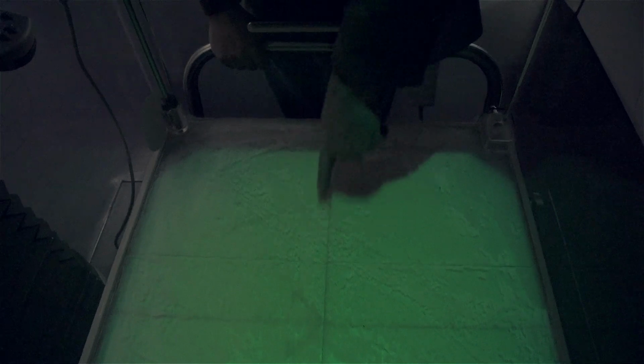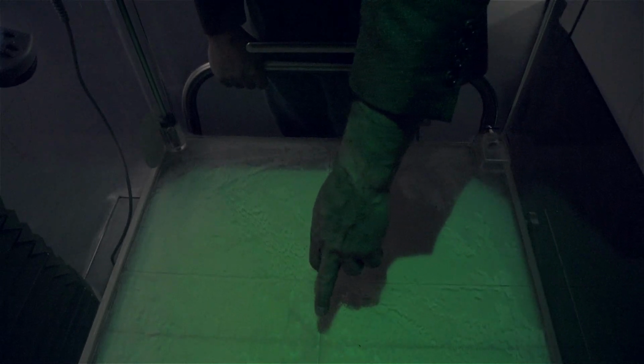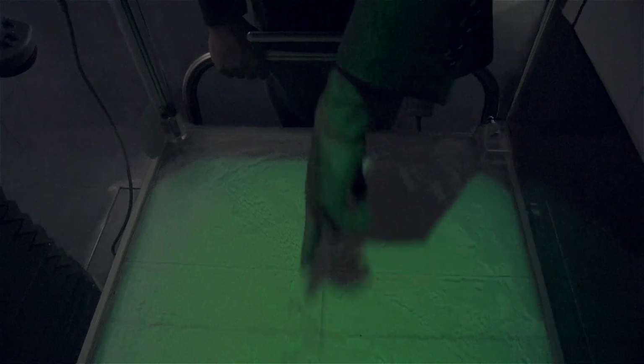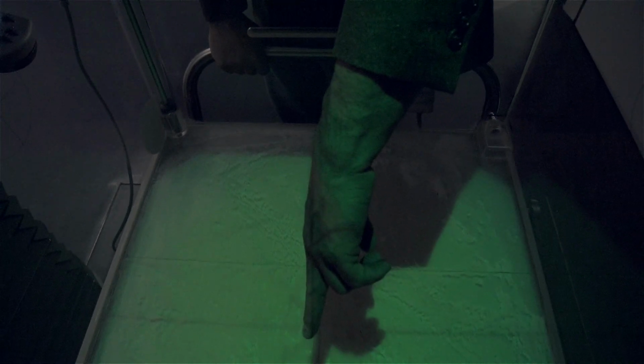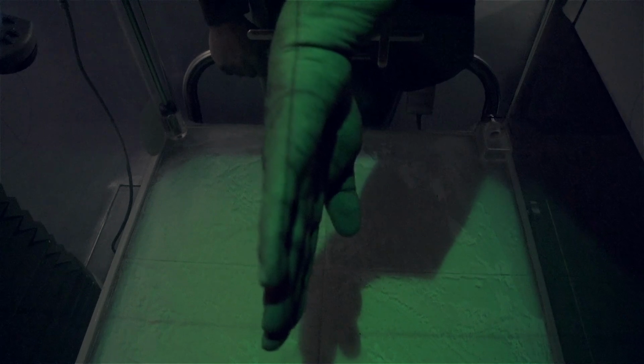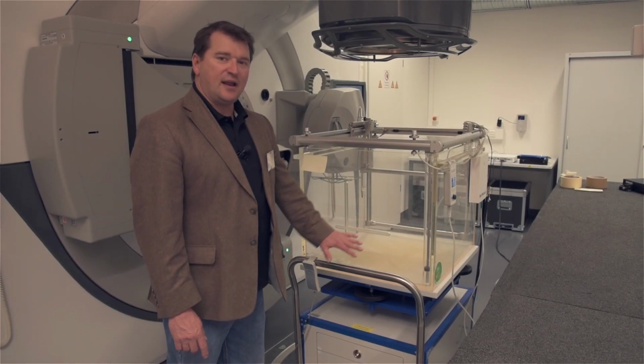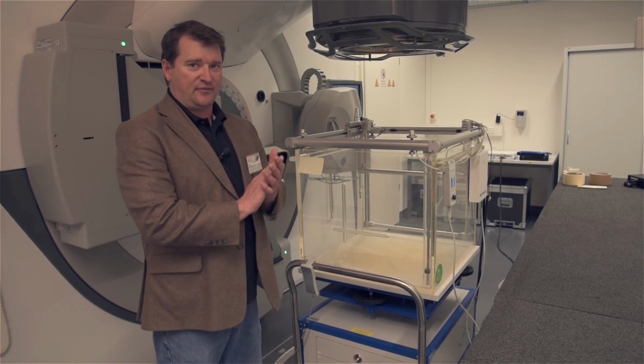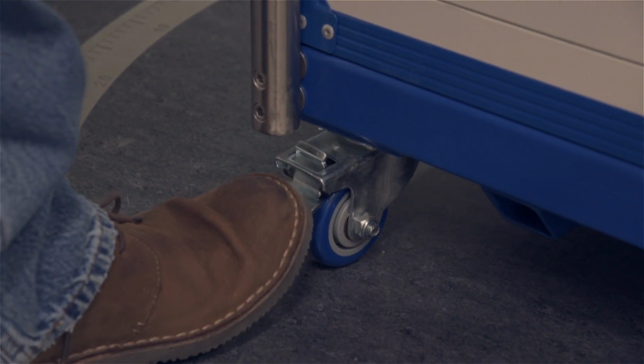You'll notice right now the crosshairs are here in the tank, and the shadow is over here. The reason I'm doing it that way is I want to align this crosshair up first and then move the tank that direction until that shadow intercepts this line. That's pretty close, and it's close enough. When we did that alignment, we got the crosshairs close, but not perfect. And then we lock the brakes down, so the lift table is not going to move now.